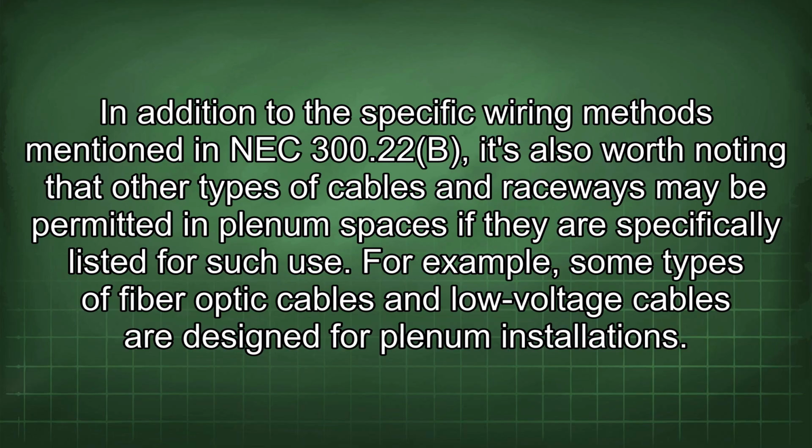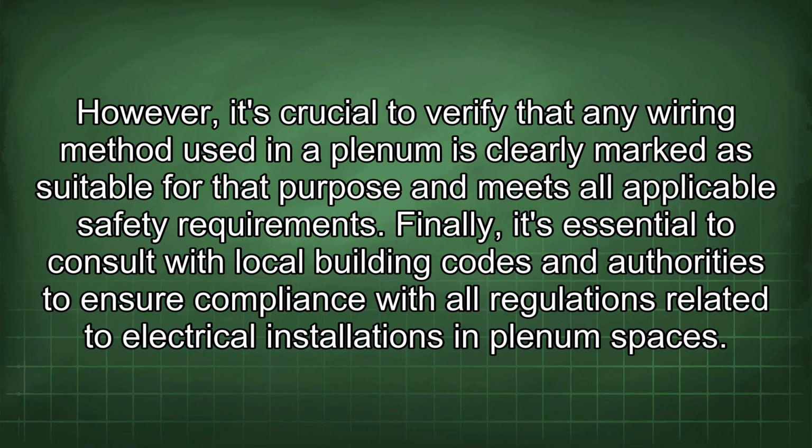In addition to the specific wiring methods mentioned in NEC 300.22(B), it's also worth noting that other types of cables and raceways may be permitted in plenum spaces if they are specifically listed for such use. For example, some types of fiber optic cables and low voltage cables are designed for plenum installations. However, it's crucial to verify that any wiring method used in a plenum is clearly marked as suitable for that purpose and meets all applicable safety requirements.